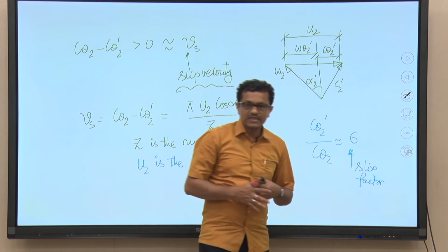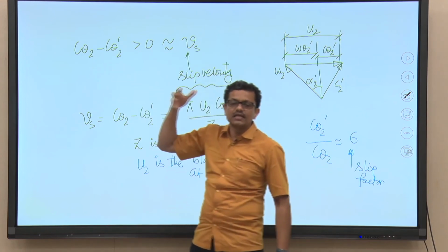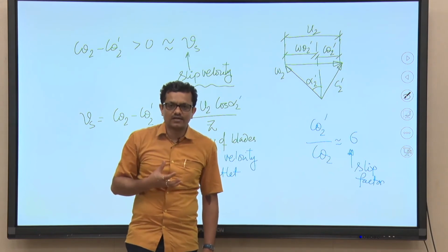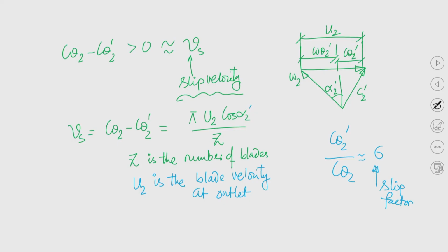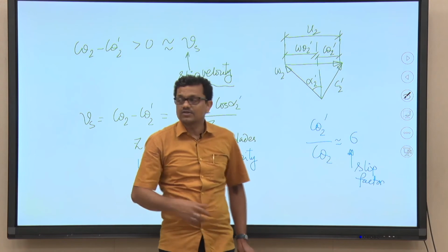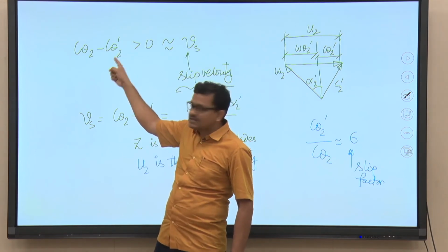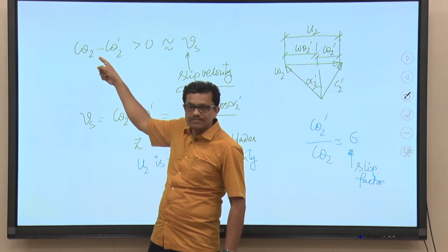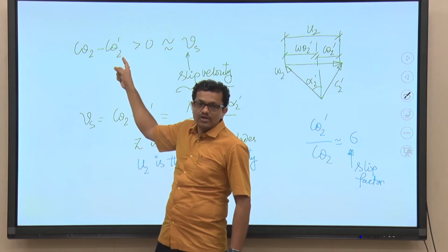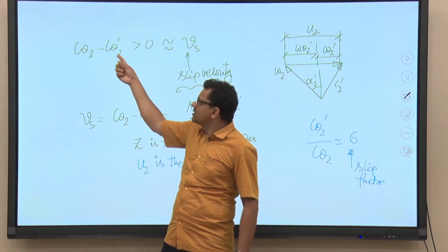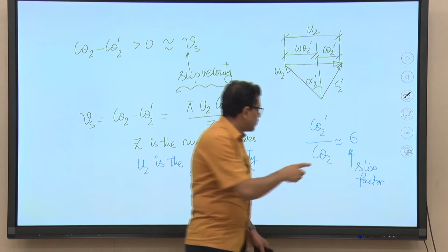So, c theta 2 is the tangential component of absolute velocity we are expecting to get, but at the moment when the pump is rotating, because of the resultant force we are eventually getting a tangential component of absolute velocity less than what we expect. So, c theta 2 prime is the diminished swirl velocity at the outlet. The ratio of these two components is known as slip factor.